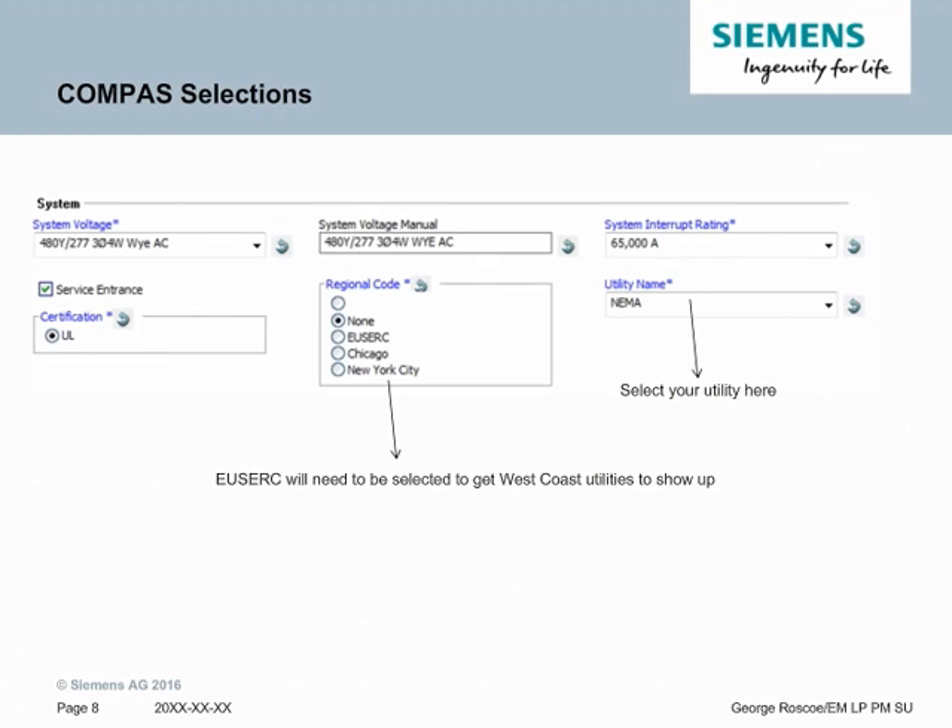Selecting a utility in Compass is fairly straightforward. On the main page at the top of the tree, right under where you select system voltage and interrupt rating, is a regional code. If it's the East, you select none. If it's also for Chicago and New York City, you'll select this. If you select none, you will get the East Coast utilities. If you select EUSERC, that is how you get the West Coast utilities. So just be aware: if you select none and look for a West Coast utility, it will not show up. And vice versa, when you select EUSERC and look for an East Coast utility, it will not show up. So those are the two key things to set in Compass for what utility metering options you will have.